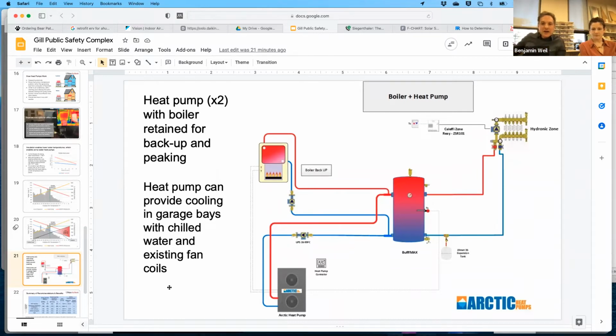So any place where you have a fan coil unit that's providing heating, it can also use the circulating water to provide heating or cooling. Whereas if you only have fin tubes, you can't do cooling because you would condense water onto it.